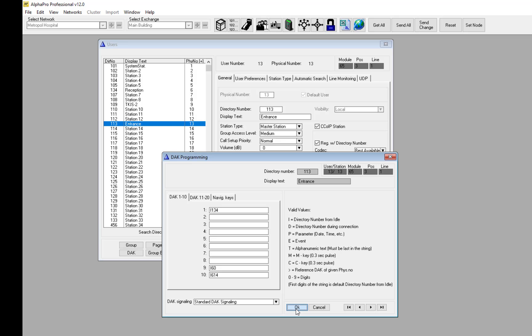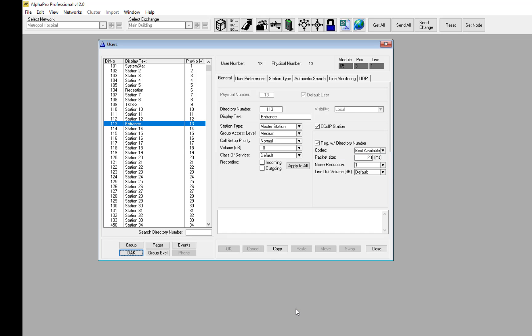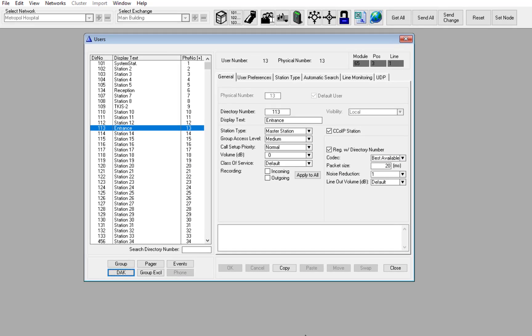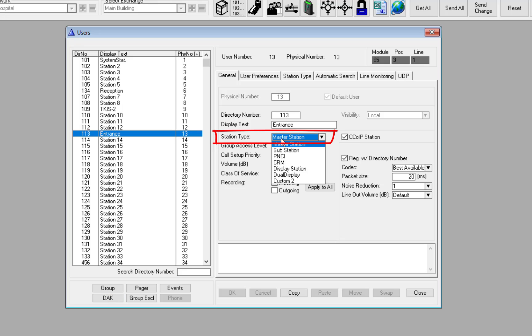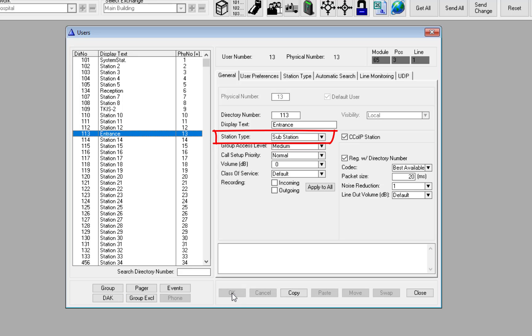AlphaPro will automatically add the letter I in front of the number. It is good practice to set the intercom station to station type substation. This will prevent accidental callback messages to the intercom.